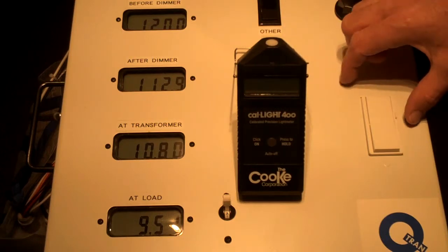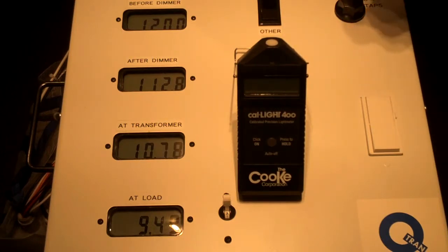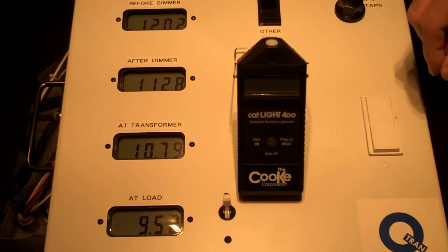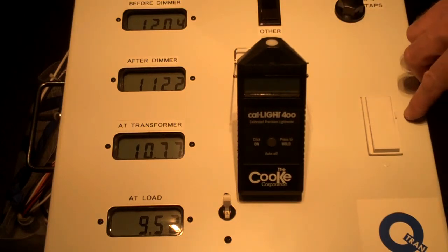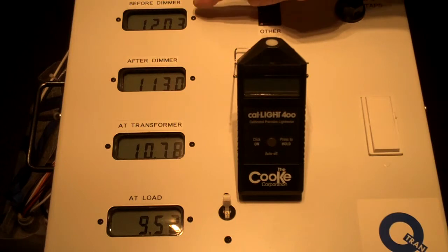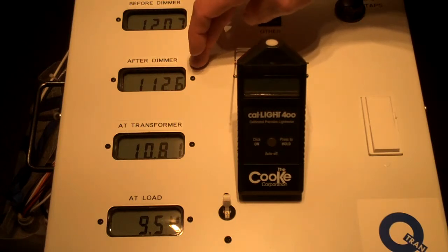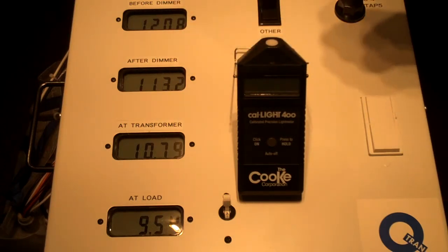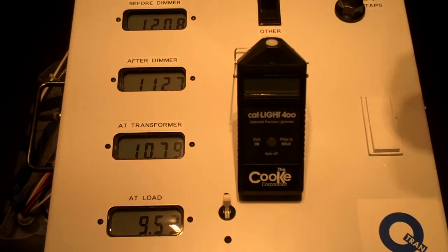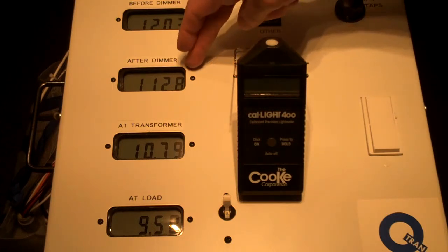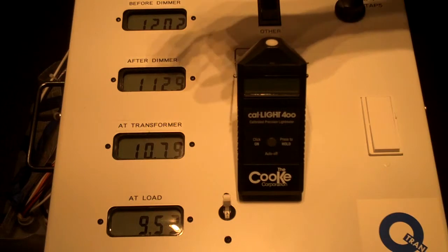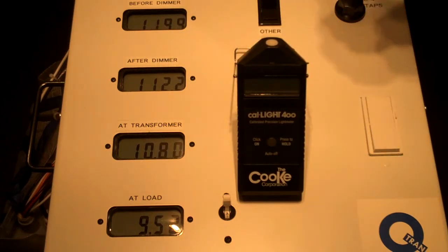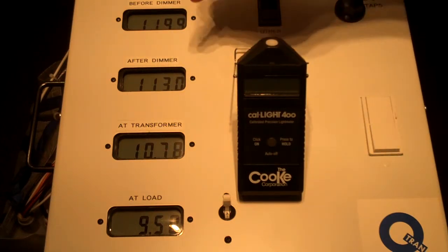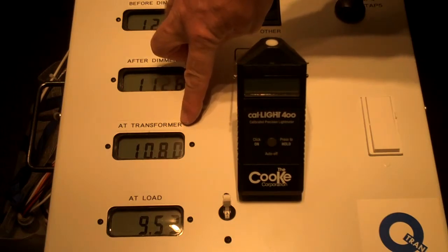And you'll notice that whenever you run through a dimmer or a dimming module of any sort, you have what's called dimming loss because it's not 100% efficient as an electrical device. So our voltage actually drops from 120 here to about 113 here. Typically about 5% of your primary voltage is lost, which means in turn that the transformer no longer sees 120 volts as its primary. It's now seeing 113 or 112 volts as its primary, reducing the secondary output on the transformer. So our transformer in here is putting out 10.8 volts right now instead of 12.